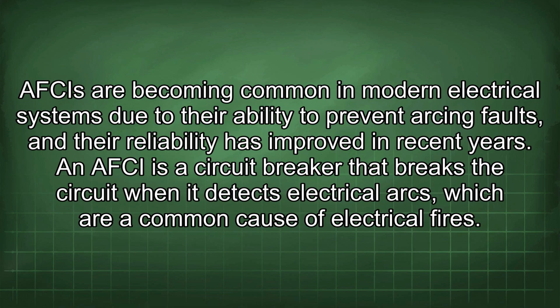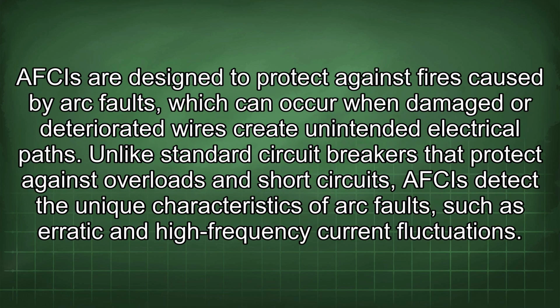AFCIs are becoming common in modern electrical systems due to their ability to prevent arcing faults, and their reliability has improved in recent years. An AFCI is a circuit breaker that breaks the circuit when it detects electrical arcs, which are a common cause of electrical fires. AFCIs are designed to protect against fires caused by arc faults, which can occur when damaged or deteriorated wires create unintended electrical paths. Unlike standard circuit breakers that protect against overloads and short circuits, AFCIs detect the unique characteristics of arc faults, such as erratic and high-frequency current fluctuations.